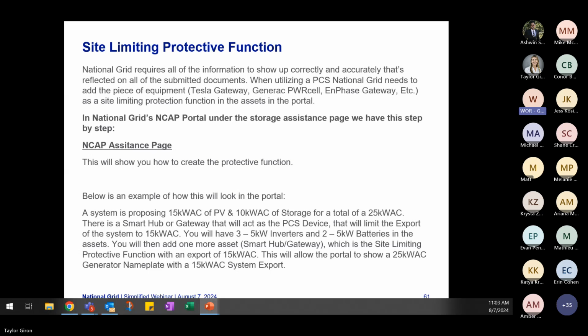Next, we'll move on to site limiting protective function. National Grid requires all of this information to show up correctly and accurately, thus reflected on all of the submitted documents. When utilizing a PCS, National Grid needs to add the piece of equipment, it can be Tesla Gateway, Generac PWRcell, Enphase gateway, etc., as a site limiting protection function in the assets in the portal. Below is the link to our stakeholder website that contains the step-by-step on how to create the protective function. The protective function asset will reflect the piece of equipment that will curtail the system. Below is an example of how this will look in the portal, but I'll leave it due to time constraints. You can visit this later and look at it. Next slide, please.